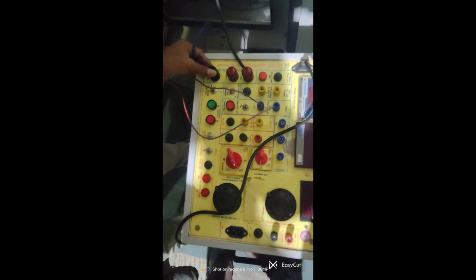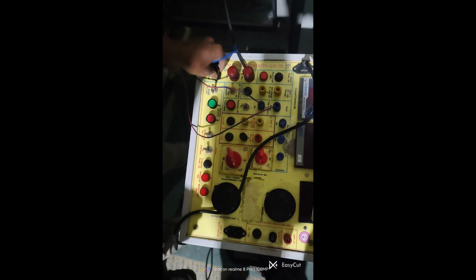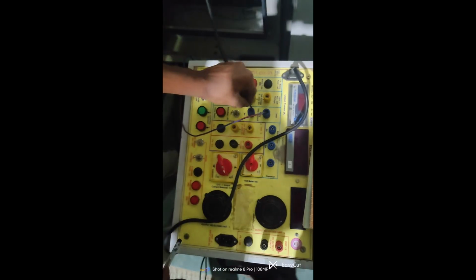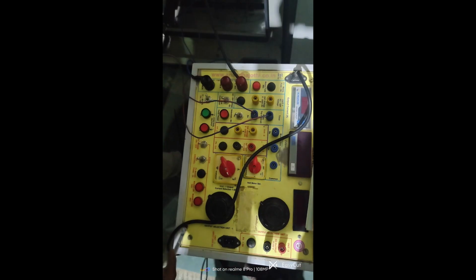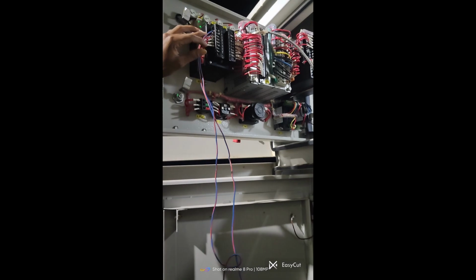Relay kit, the current injecting cable. We can inject the secondary side, CT secondary side. We are injecting, and there are two cables for feedback, taken from the 86 NO-NC contact. Now we can take the NC contact.